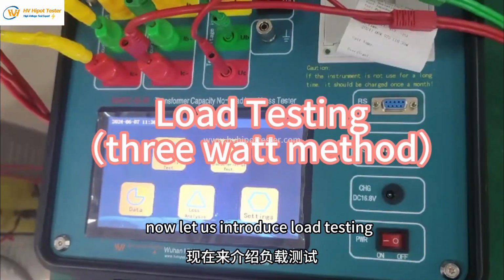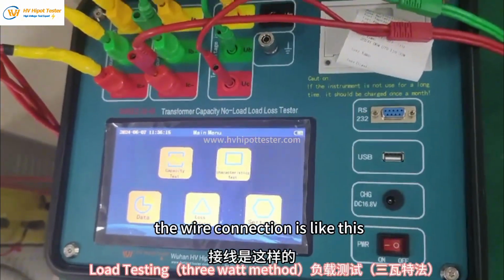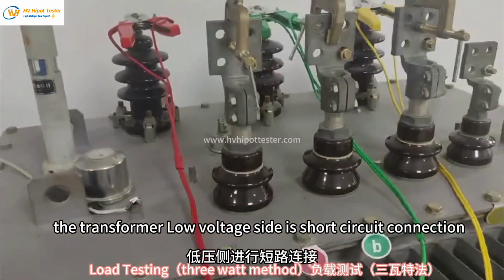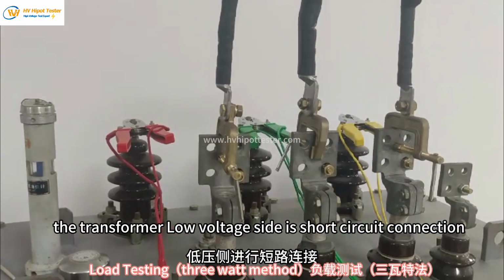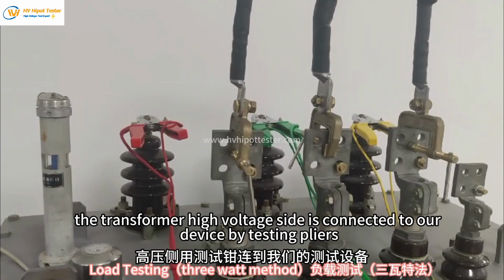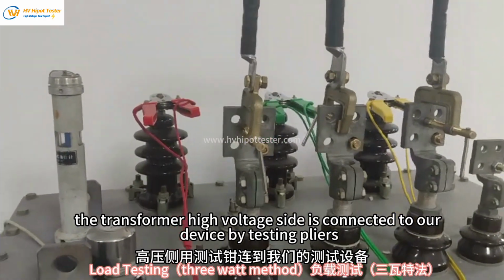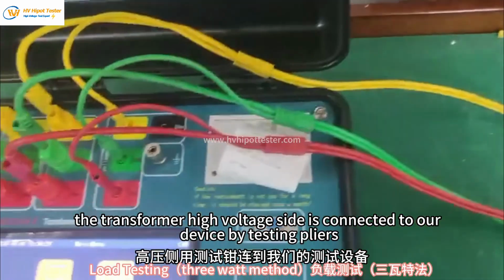Now let us introduce load testing. The wire connection is like this. The transformer low voltage side is short circuit connected. The transformer high voltage side is connected to our device by testing pliers.